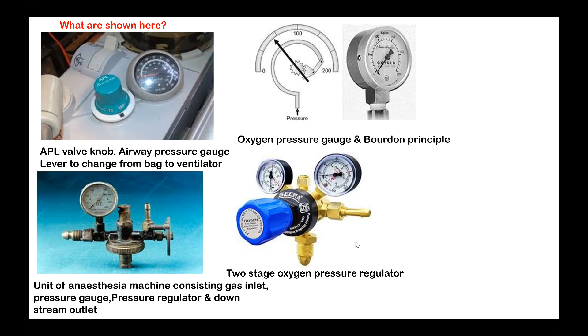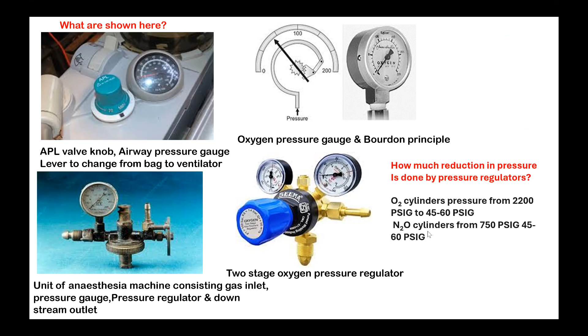This is again a head of an attachment where you can do what is called two-stage regulation. You can reduce the pressure to a higher level and then to a lower level. So this is called the two-stage oxygen pressure regulator. And how much pressure reduction is happening by the pressure regulator from 2000 psi or 1900 psi from the full cylinder? What is the pressure to which it is reduced before it reaches the flow meter? 45 to 50 psi. 50 psi. Good. So nitrous oxide will come to 60 psi.